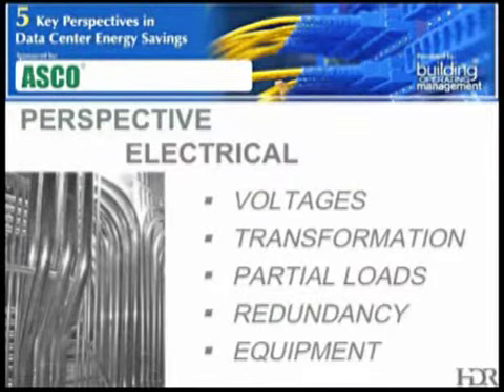Ideally, we want to stay at the highest possible voltage to reduce interim transformation levels. We want to understand where transformation occurs and how it affects the system. One of the things that we're hearing a lot now is about going to a European standard type distribution with 230/400 volts. And that's nice because the power supplies for the servers operate more efficiently at the 230 volt level than they do at the 120/208 volt level. The higher voltage means less line losses and greater capacity for the same amount of distribution wiring.